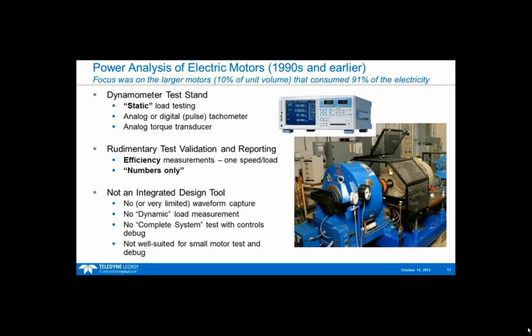Motors historically, especially big ones like AC induction motors, are tested on a test stand. The test is usually a static load test, so a single load, with an analog tachometer signal and an analog torque transducer feeding data to calculate mechanical power. The device that calculates mechanical power could be a power analyzer, which also calculates electrical power and efficiency. This isn't an integrated design tool—it has limited waveform capture, doesn't provide dynamic load measurements, doesn't let you look at control signals coincident with power signals, and isn't well suited for small motor test and debug.